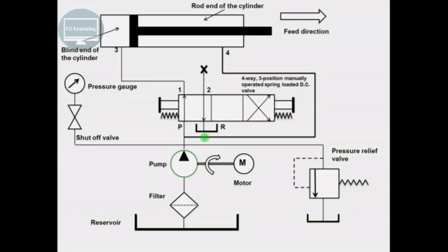When the spool of the four-way direction control valve is in the left envelope mode, fluid flows from the reservoir through the filter, to the pump, to port P, from P to port 1, from 1 to port 3, and enters into the blind end of the cylinder, causing the piston and piston rod to move in the forward direction.